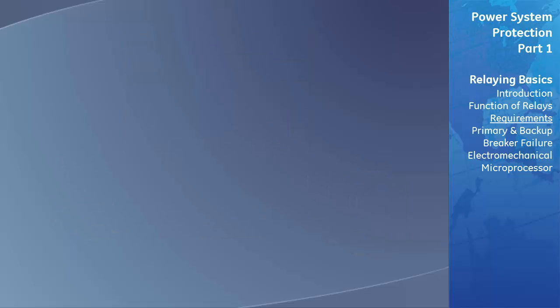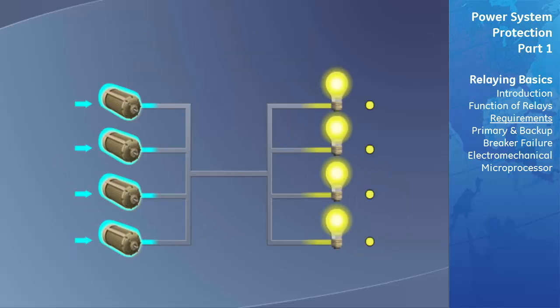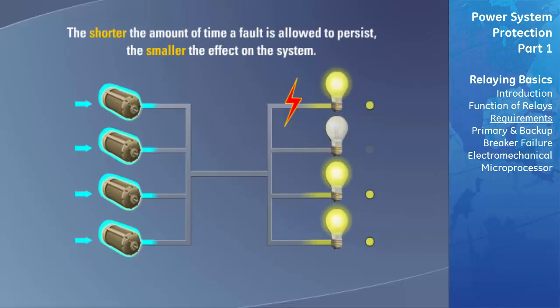The speed of operation also has a direct effect on the general stability of the power system. During a short circuit fault, the rest of the power system can transmit less power because the various sources of generation tend to go out of synchronism. The shorter amount of time a fault is allowed to persist, the smaller its effect is on synchronism or stability of the system.